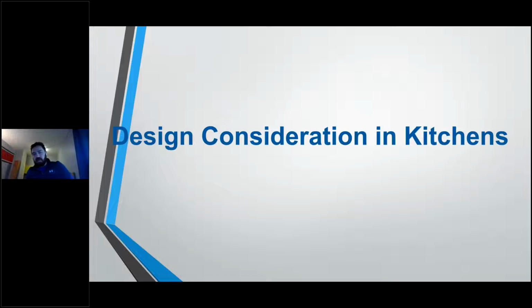And then from there, there's only a couple of design considerations to think about for mitigating problems that can come up with your design. The biggest question in design considerations is going to have to do with your makeup air. Am I going to utilize a heat-only makeup air, a heated and cooled makeup air, or a full DOAS unit with heat, cool, and dehumidification, and the different price points of not only your initial product, but also your ongoing energy consumption, which we'll get into.